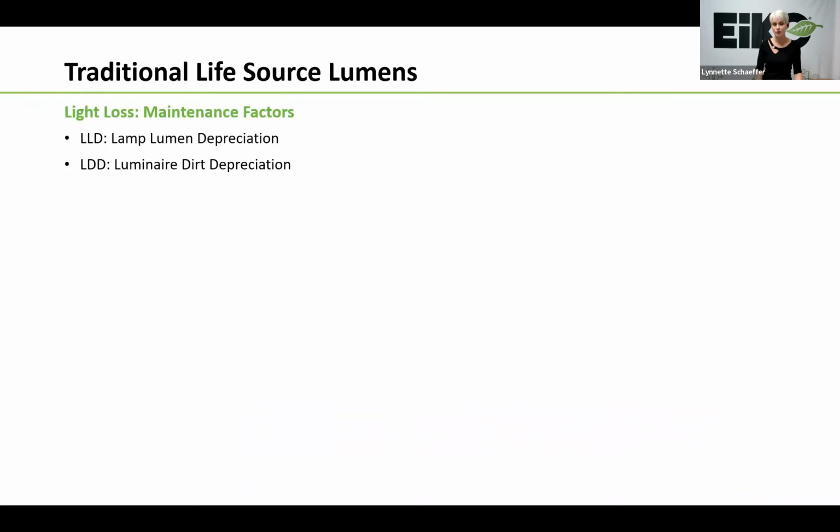So speaking of lumen output, when lamps lose lumens, we call it lumen depreciation. Now, nearly all lamps, including LEDs, have some kind of lumen depreciation, which basically just means that the light source ages. As it ages, it produces a much lower light than it did on day one. So as we just mentioned, fluorescents lose about 5%, metal halides about 40%, and high pressure sodiums about 15%. LEDs lose a substantial amount, but it just takes longer for that process to happen. And you're going to hear about that in a different training video.